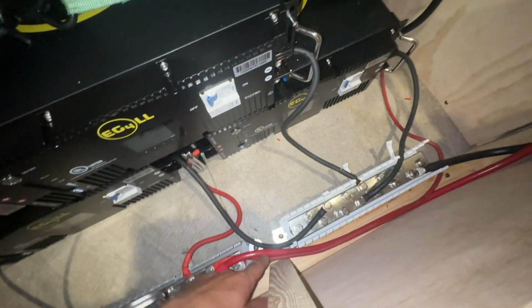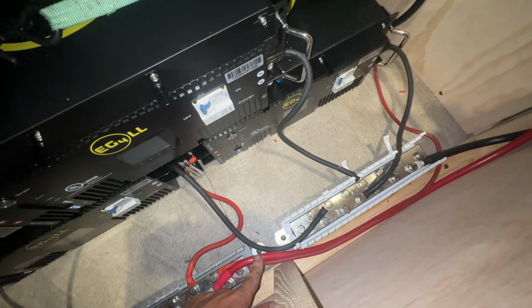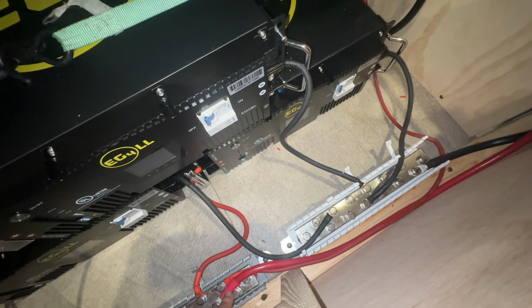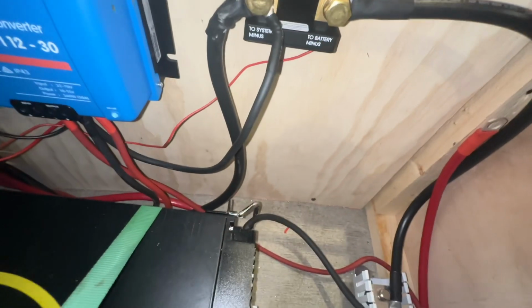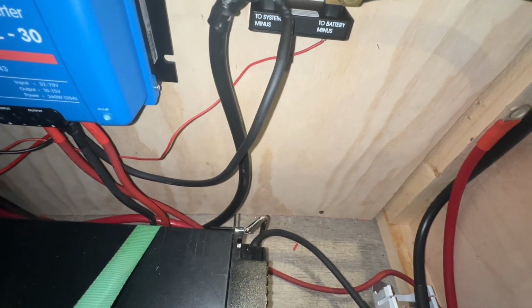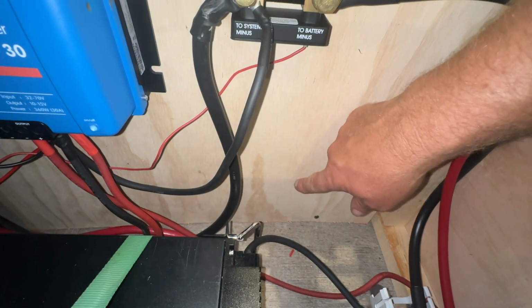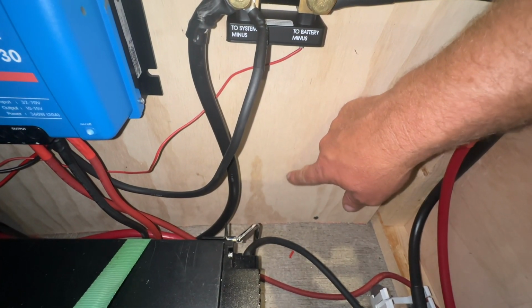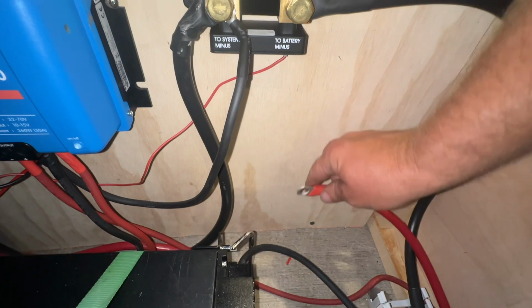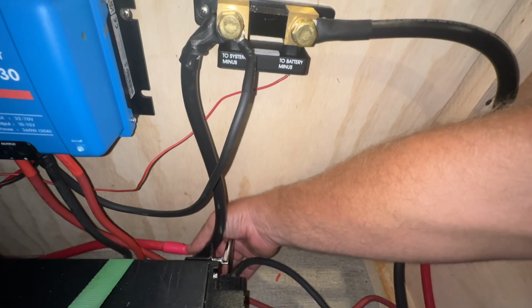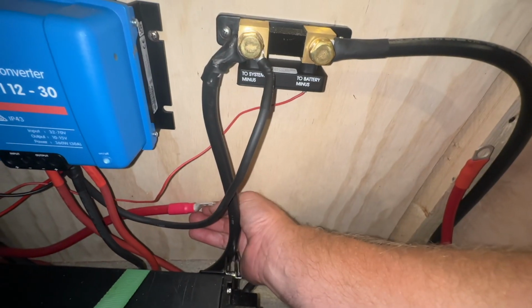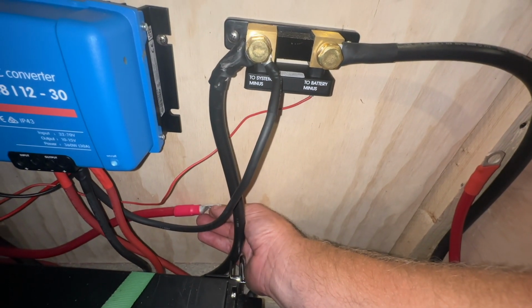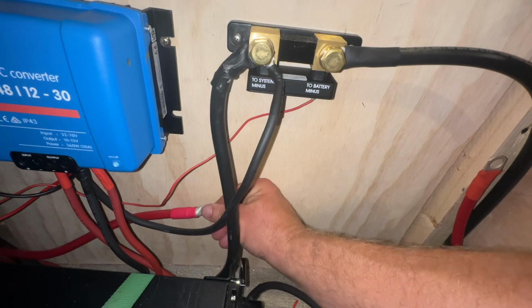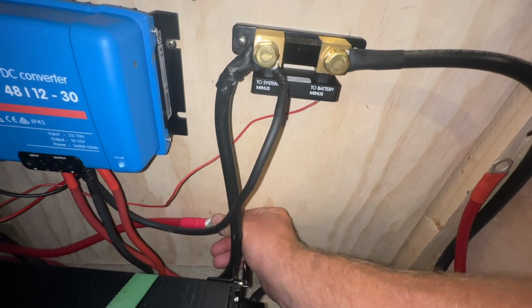Then over here I have a 1 gauge wire going from the positive bus bar. They don't tell you that you need it, but I decided I wanted extra protection anyway. I'm waiting on a 300 amp T-fuse which is going to mount right here. This goes into the T-fuse, and this is the other side from the T-fuse, and this goes out to the circuit breaker, which then feeds into the inverter.